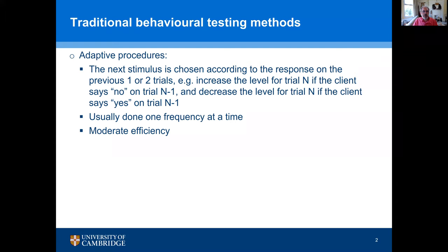Traditional methods for testing in audiology — for example, measuring the audiogram — use an adaptive procedure where the next stimulus is chosen according to the response from the previous one or two trials. For example, increase the level for trial n if the client says no on trial n minus one, and decrease the level if the client says yes. This is usually done one frequency at a time, and it has only moderate efficiency — it takes longer than it needs to take.